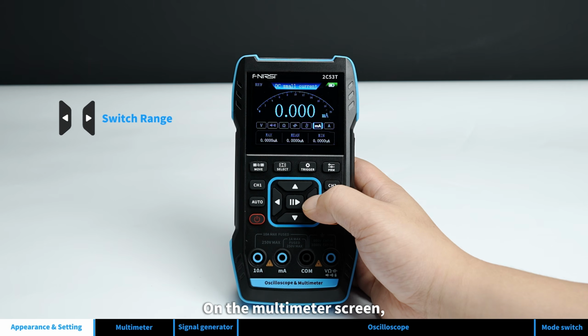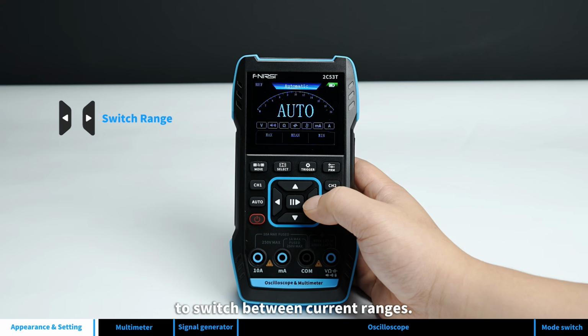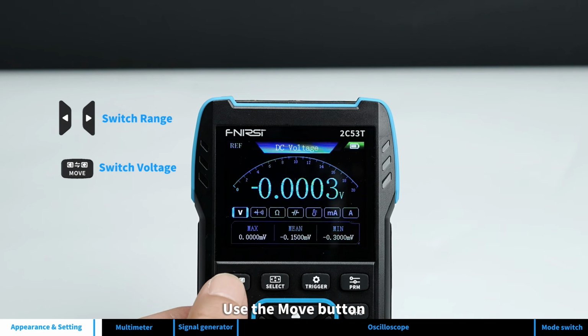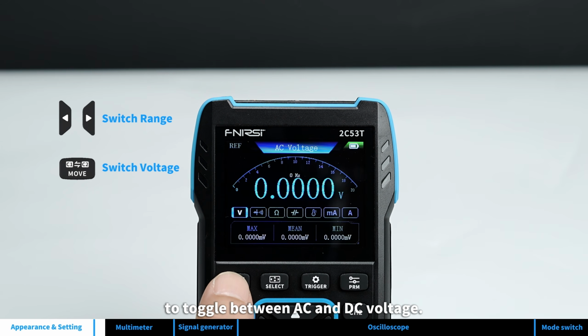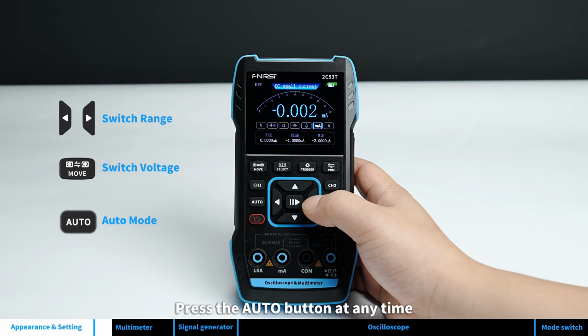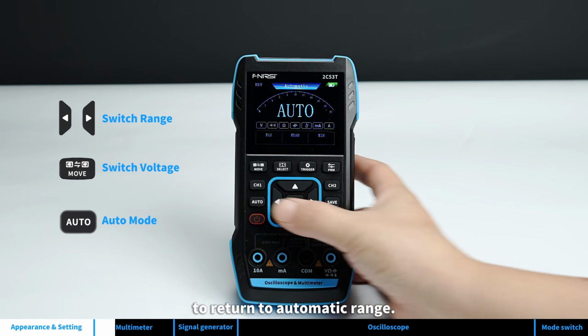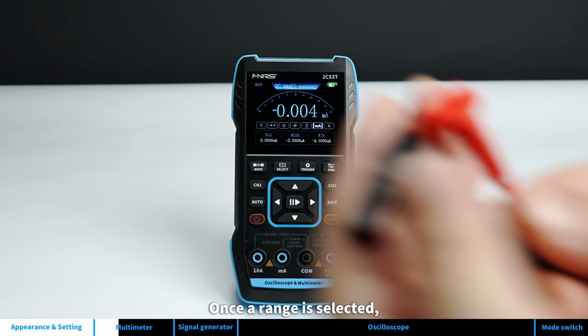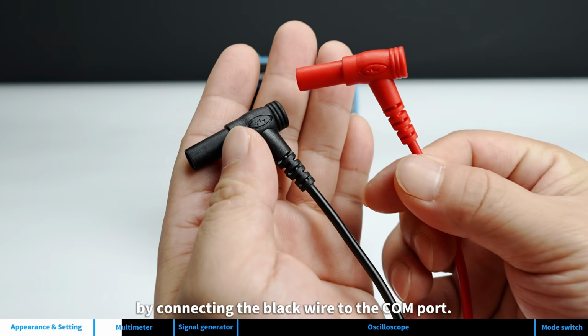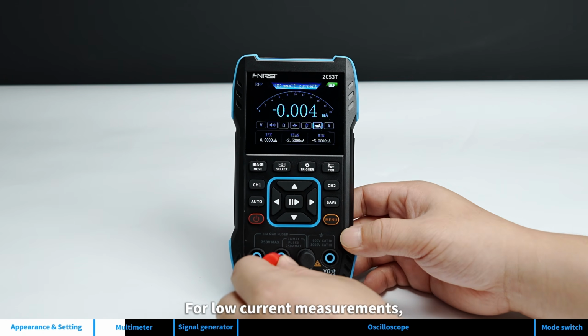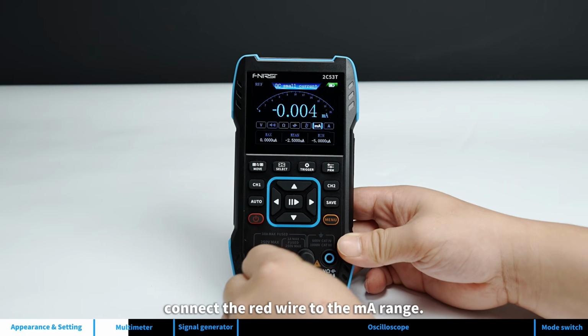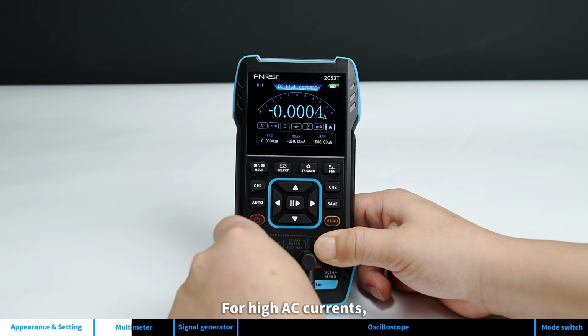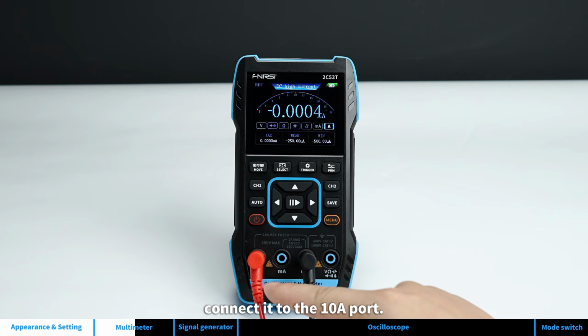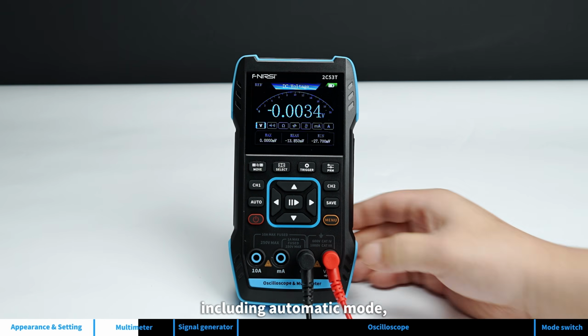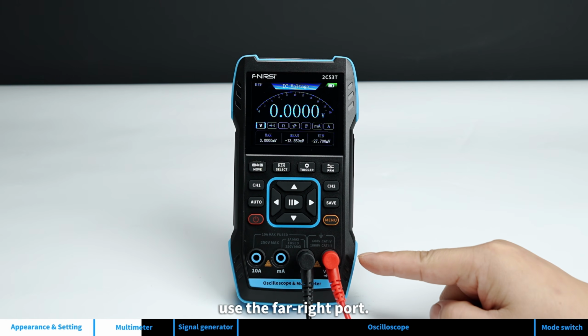On the multimeter screen, use the left and right buttons to switch between current ranges. Use the move button to toggle between AC and DC voltage. Press the auto button at any time to return to automatic range. Once a range is selected, start wiring by connecting the black wire to the COM port. For low current measurements, connect the red wire to the milliamp range. For high AC currents, connect it to the 10 amperes port. For other ranges, including automatic mode, use the far right port.